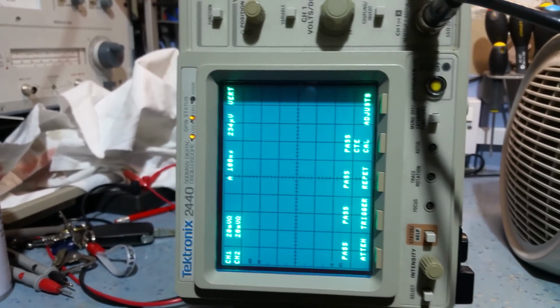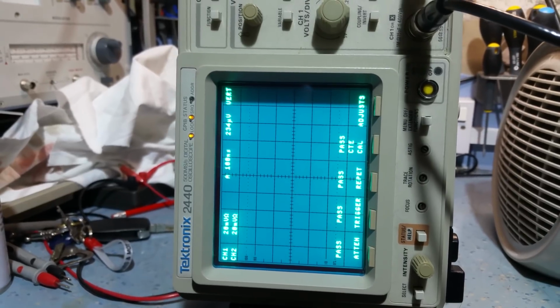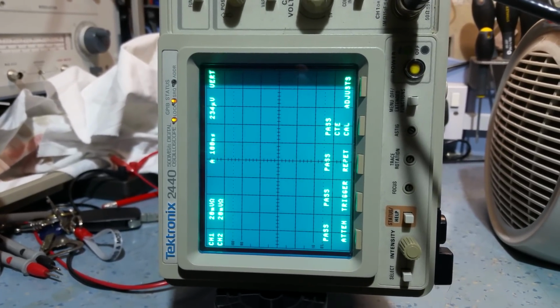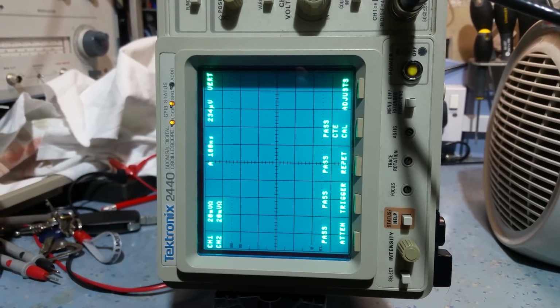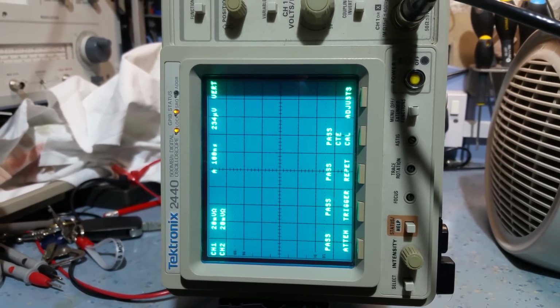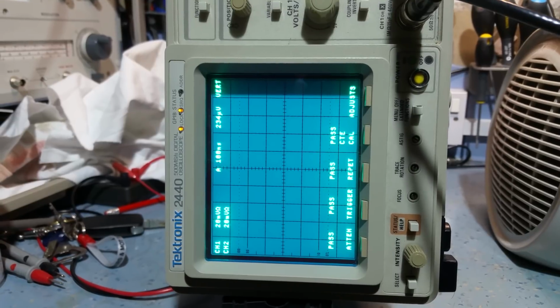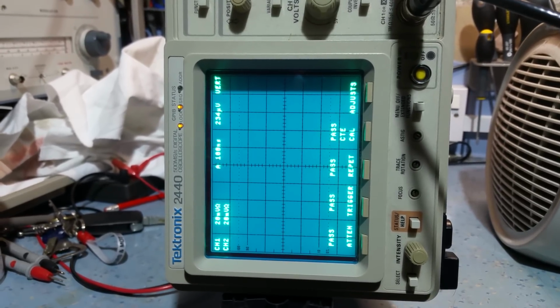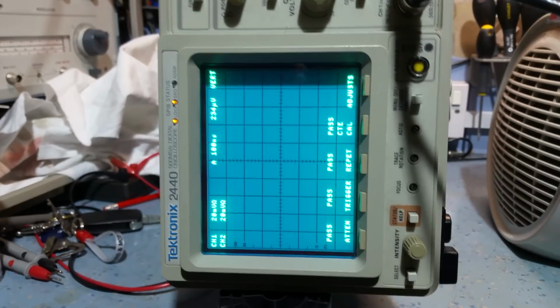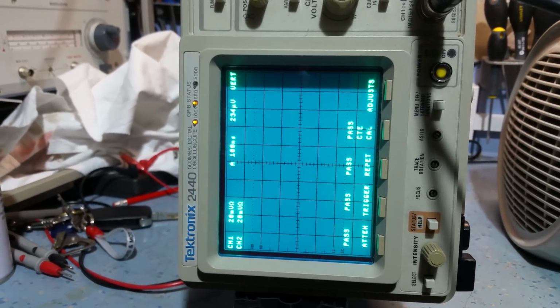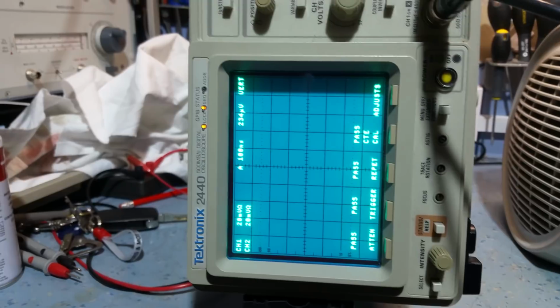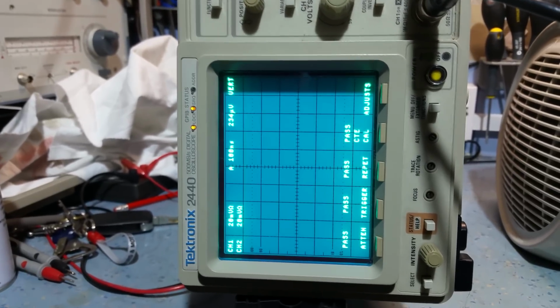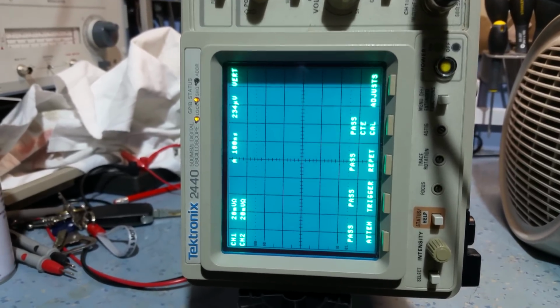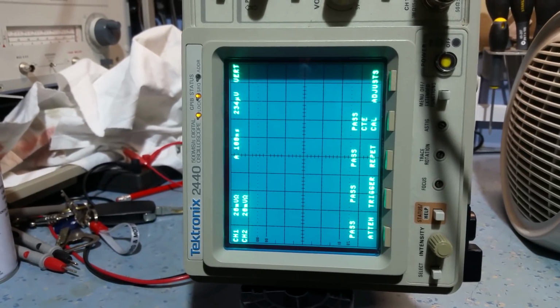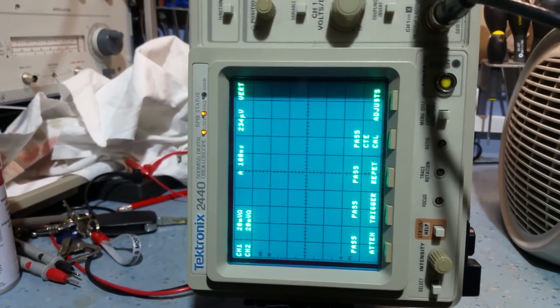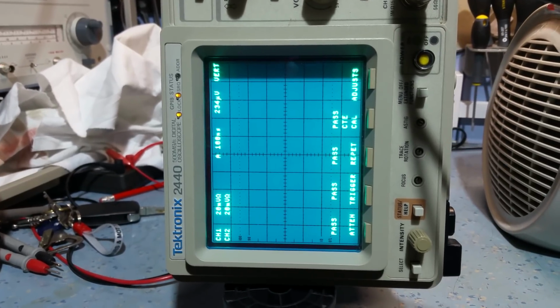It's working. Now, the reason why it was saying the non-volatile RAM was corrupted was what happened when I was doing a self-diagnostics, it wasn't completing. So what I was doing was turning the power off and back on again. And of course, it was halfway through a calibration process, so it corrupted all the data. Okay, so that's the reason why it kept doing that. So that aside, there's nothing actually wrong with the processor board as such. It's because I was turning it off in the middle of a calibration process.